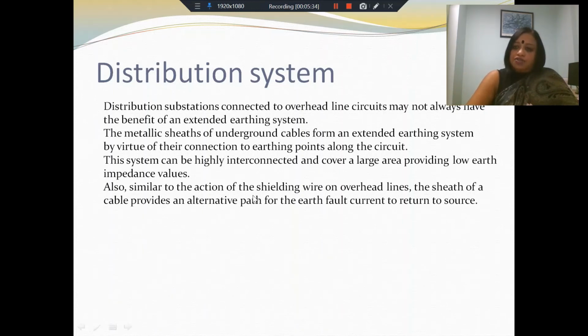Also, the sheath of the cable provides an alternative path for the earth fault current to return to source, and in this way, the path is divided between the earth and the sheath. So there are several paths through which the fault current can return to source, just as in the case of the overhead shield wire. The shield wire provides an alternate path for the fault current to return to source. So when you break up the fault current and provide it with several alternate paths, naturally the potential rise along one path reduces.